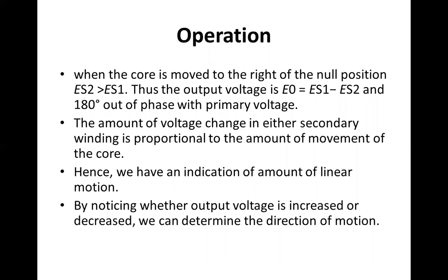When the core is moved to the right of the null position, then ES2 will be greater than ES1. Thus the output voltage is E0 equals ES1 minus ES2 and 180 degrees out of phase with primary voltage. The amount of voltage change in either secondary winding is proportional to the amount of movement of the core. Hence, we have an indication of amount of linear motion. By noticing whether output voltage is increased or decreased, we can determine the direction of motion.